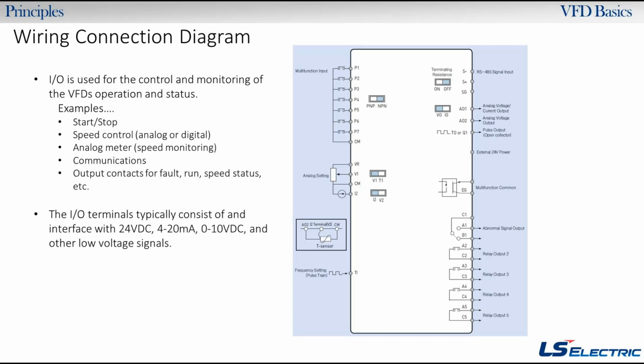So that's all what we're going to talk about here. I/Os are typically meant to interface with 24 volt DC or dry contacts. So you don't want to put 120 volts on these. They're all optically isolated optocouplers. If you put AC voltage on them, they're going to blow out and they're not going to last very long. So just be aware of that.